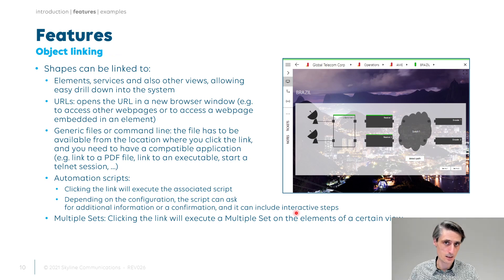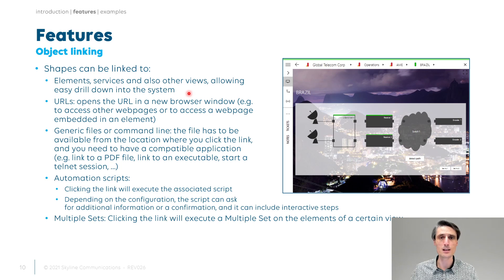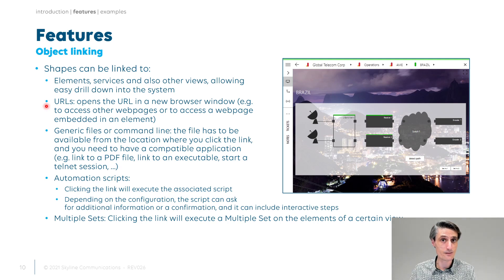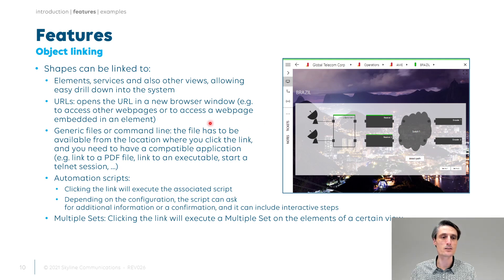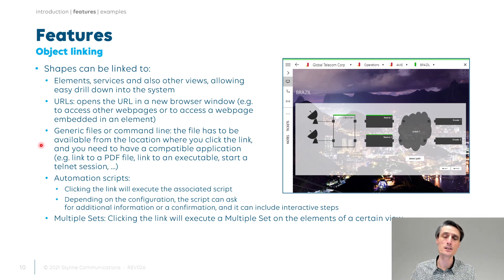We can link to many other things as well. Instead of linking to an element, we can link to services, to other views to drill down to another site, or to other elements. We can also link to URLs, allowing you to show a web page embedded inside the graphical presentation, or with a click of a button it opens up in a new tab page. We can add buttons on there, and we can also link to generic files, documentation, but also command lines — so a button that immediately opens up documentation, or a button that opens up a Telnet or RDP session.